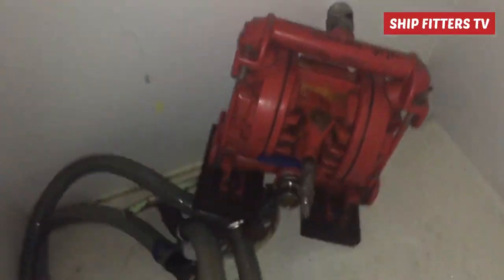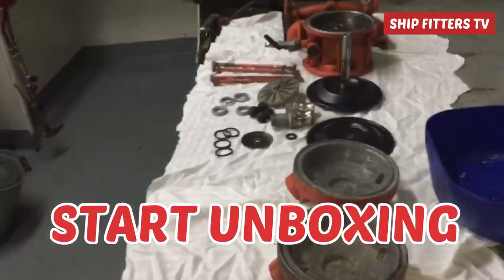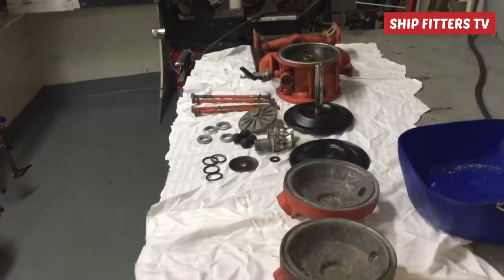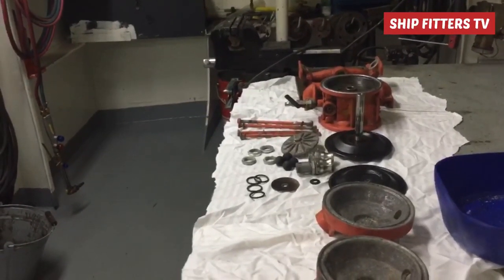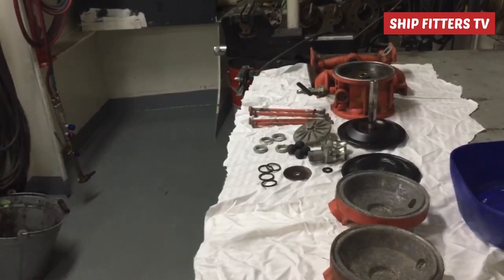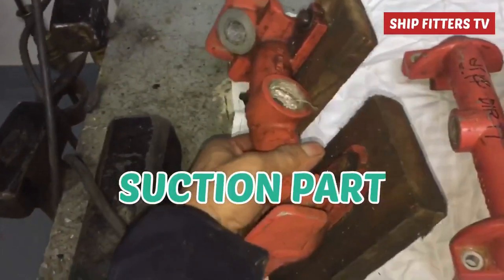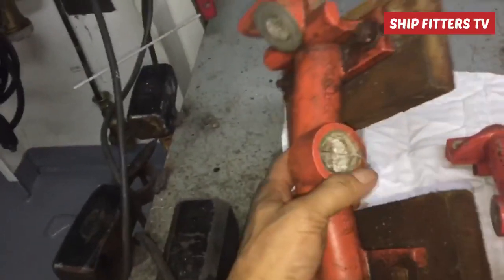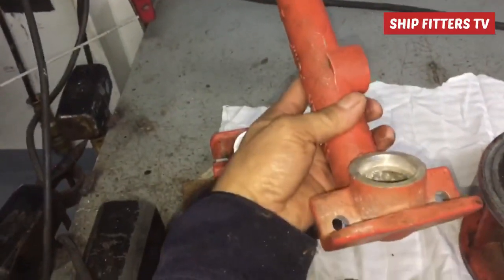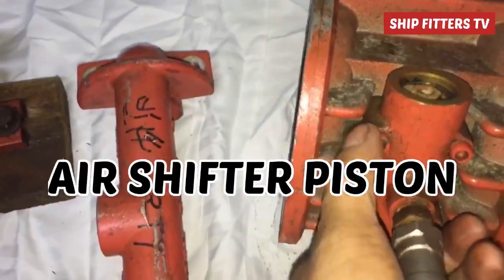We need to bring this Wilden pump to my workshop to dismantle and investigate what's inside. After dismantling, I found out the main problem — why it cannot take suction and also cannot discharge — because of the valve seat. The suction line is already in good condition, and the discharge line has no plugging or blockage. The body is also in good condition.